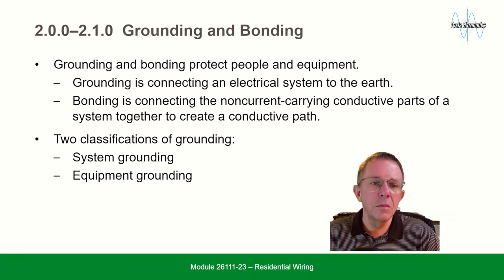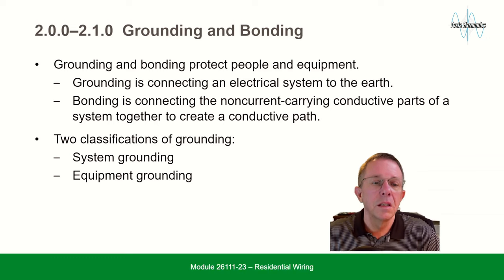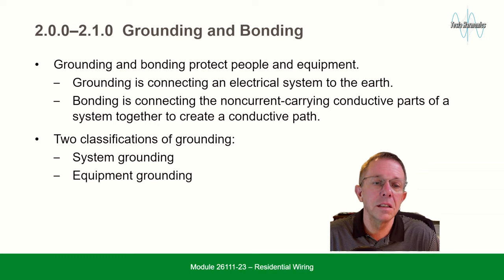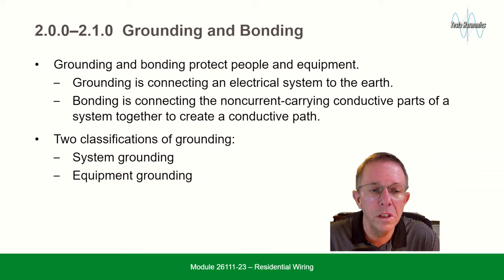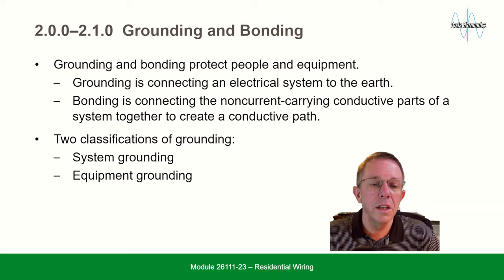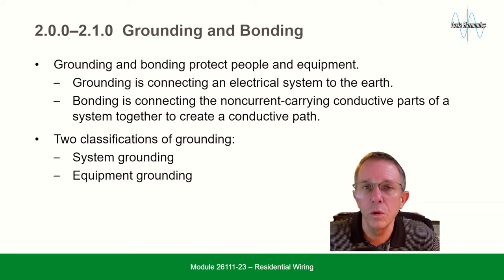Grounding and bonding protect people and equipment. Grounding is connecting an electrical system to the earth. Bonding is connecting the non-current-carrying conductive parts of a system together to create a conductive path. There are two classifications of grounding: system grounding and equipment grounding.